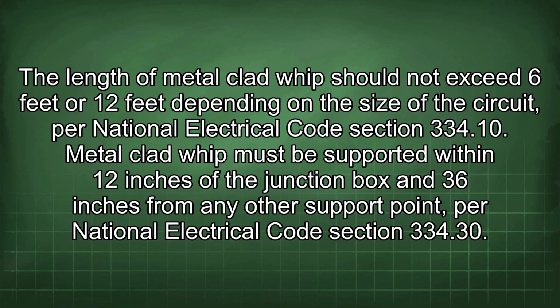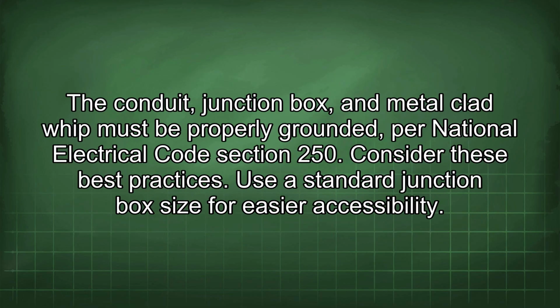Metal-clad whip must be supported within 12 inches of the junction box and 36 inches from any other support point, per National Electrical Code Section 334.30. The conduit, junction box, and metal-clad whip must be properly grounded, per National Electrical Code Section 250. Consider these best practices. Use the standard junction box size for easier accessibility.